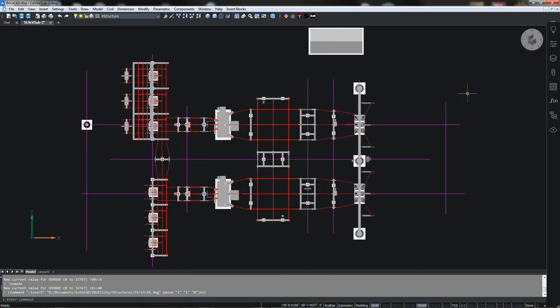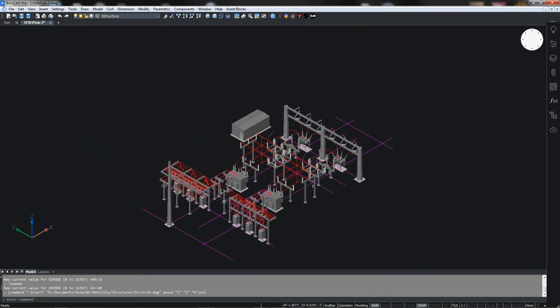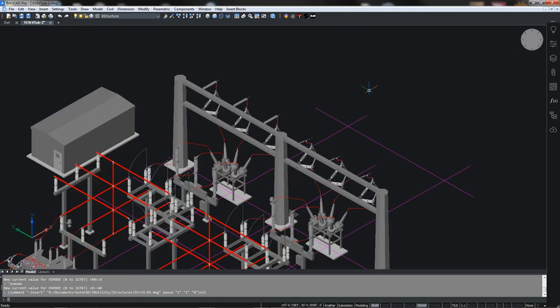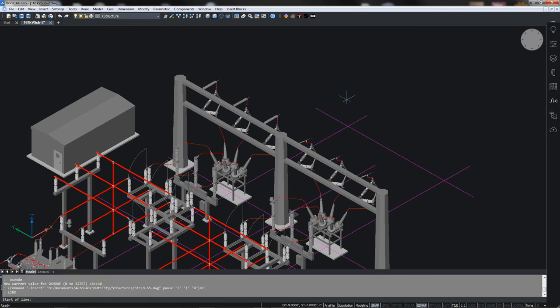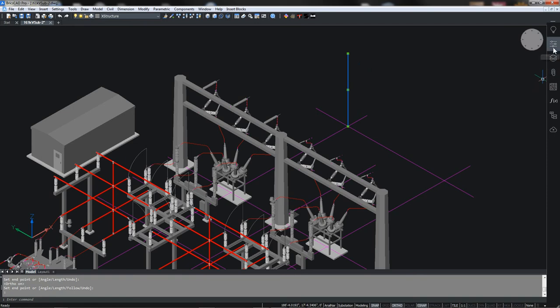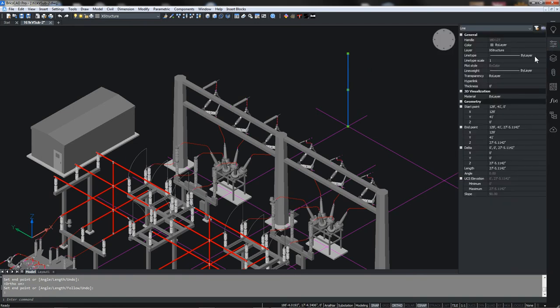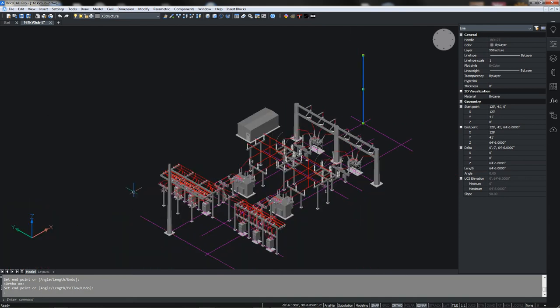Our initial design we want to look at is to lay out an overhead ground wire that goes directly over the center of the transformer. We need another attachment point. We're going to assume there's a dead end pole here where it drops into the station, so we're going to run the static from here to that dead end point. To simulate that I'm going to place a line here, and then use our properties editor to change this length. To make all of our calculations simpler in the design, we're going to set that to 64.5 feet, assuming that's the height of the static on our lightning mast. It's a 65 foot mast and the attachment point is six inches below the top.